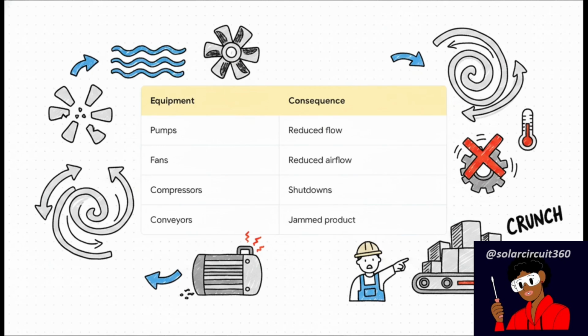If a centrifugal pump runs backward, it doesn't just pump backward. It usually just thrashes the water around. This results in drastically reduced flow and pressure, risking cavitation that can literally tear the impeller apart. And it destroys mechanical seals. With ventilation fans, backward rotation severely reduces airflow.